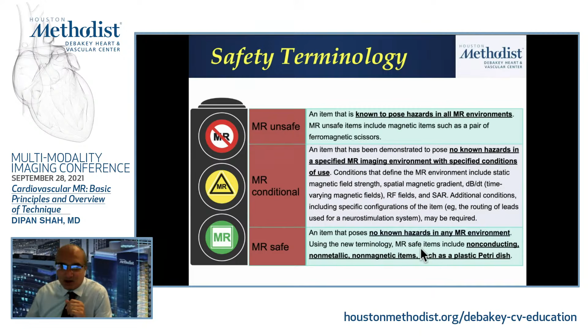And so that's why, in general, unless it's something like plastic, where it has no metallic components at all, most objects we refer to not as MRI safe, but rather as MRI conditional, which just means that in the set of settings that they've been evaluated in, there's an acceptable risk-benefit profile. Some of the classic guardrails would be, let's say, a certain pacemaker. Most pacemakers or defibrillators have been tested to be MRI conditional at the 1.5 Tesla scanner. That doesn't mean you can then take them into a 3 Tesla scanner, because you're talking about a much stronger magnetic field. The interactions can be very different, and it certainly doesn't apply to a 7 Tesla scanner.